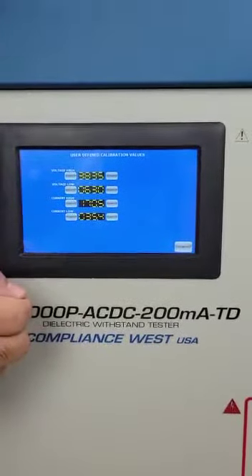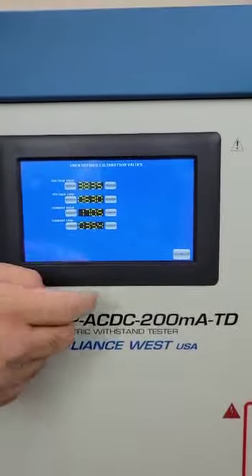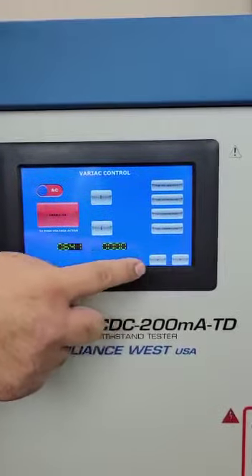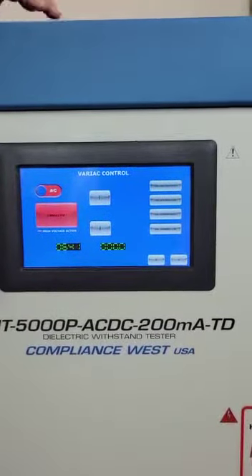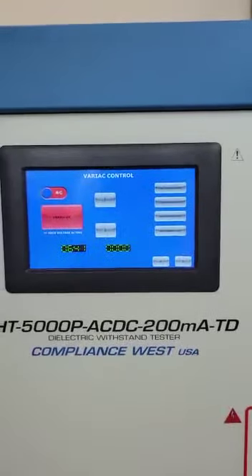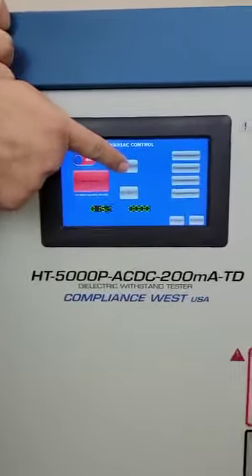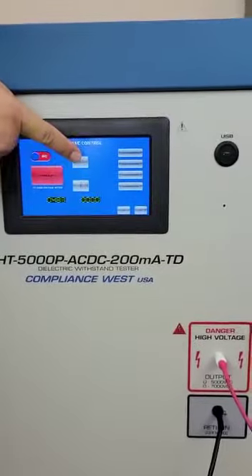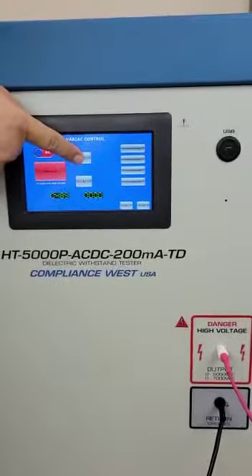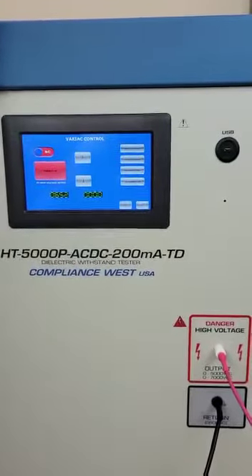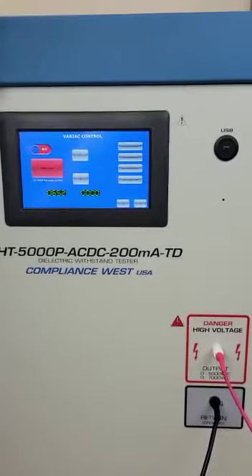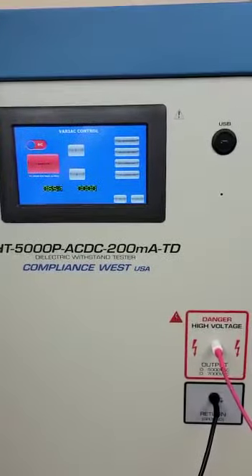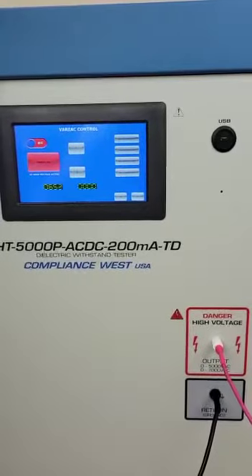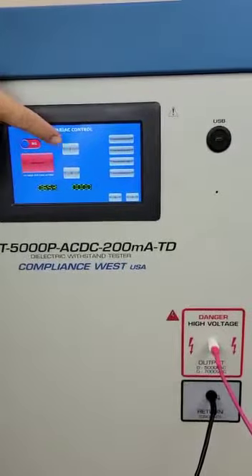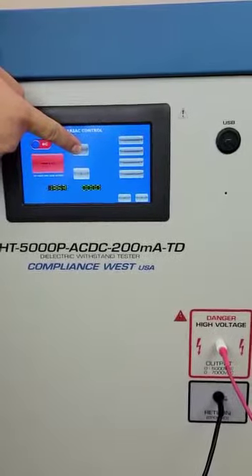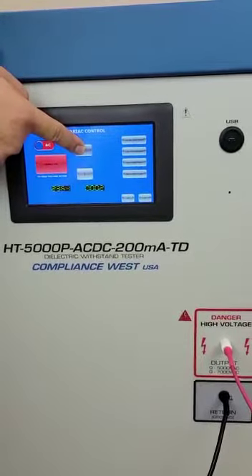We need to repeat the process for the high voltage. We go to the next screen, we leave it in AC, we press test, like that, enables the high voltage. And then for the high voltage, the high point, we recommend on AC something around 3500 volts. So we increase the output to that value or something close.